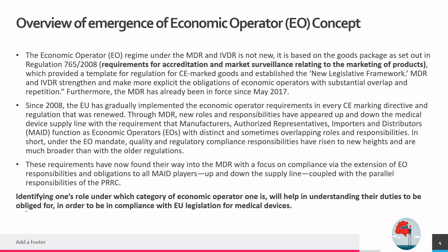Which provided a template for regulations for CE marked goods and established the new legislative framework, NLF. So MDR and IVDR strengthen and make more explicit the obligations of economic operators, with substantial overlap and repetition.